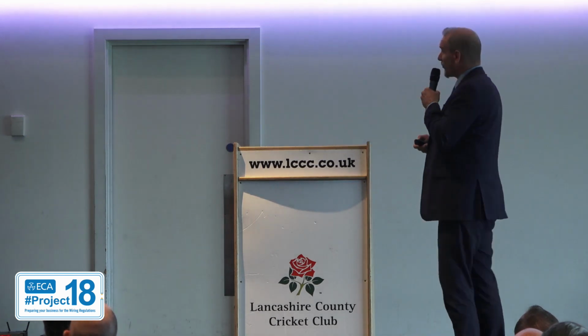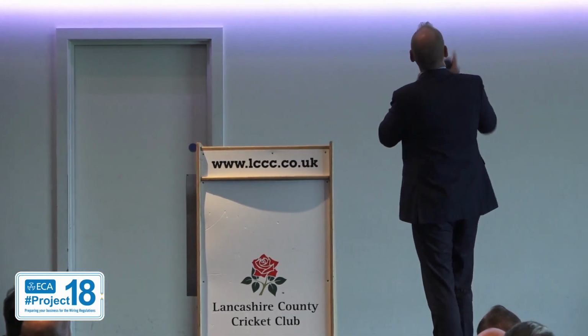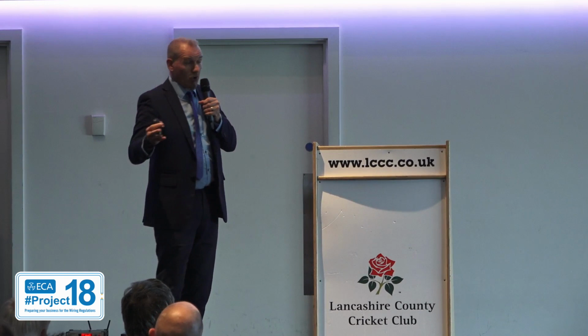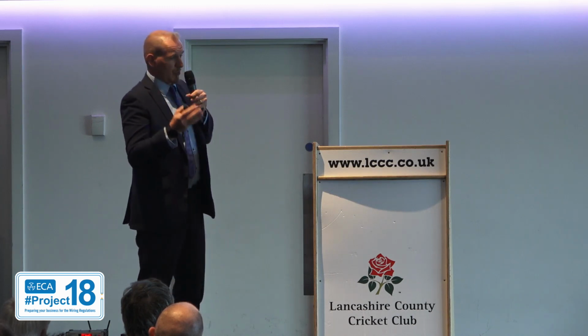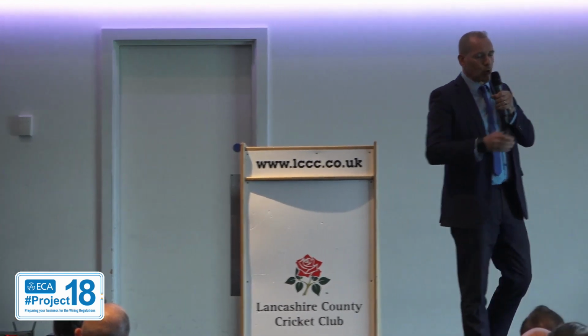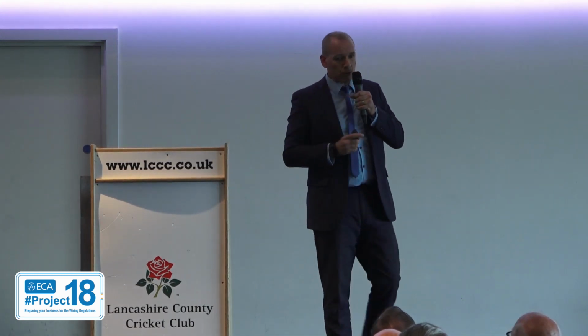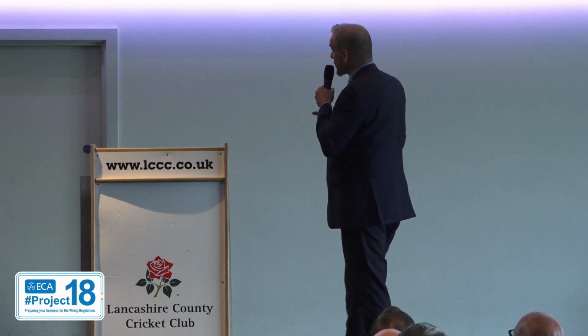We've got some problems here. There's a possibility that the fire might spread, but we've also got some zones out of commission. So what we need to do is find a different way out of the building. What we need to remember here, though, is while we're doing that, under the 17th edition, those other zones have a less rigorous cabling requirement. So there's actually a danger to people trying to leave the building, but also for people who are coming into the building. That's fire crews, that could be police, emergency services, ambulance, that type of thing. Those people coming into the building are also in danger in those zones because there's a less rigorous cabling requirement, and in those areas cables could be susceptible to premature collapse.